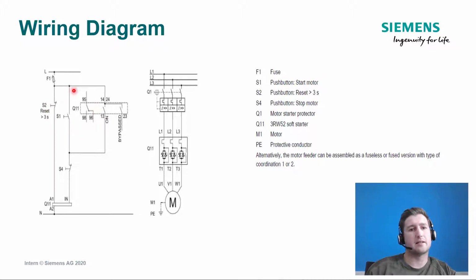And then lastly, we have, as you can see here, the changeover contact, which shows faults and warnings. That's not been connected in here, but if you want to, you can wire an external signaling device. Further to that, as you can see here, this isn't actually essential, but we have wired in the on signal. So that is just telling us that the device has been switched on through an external signal.